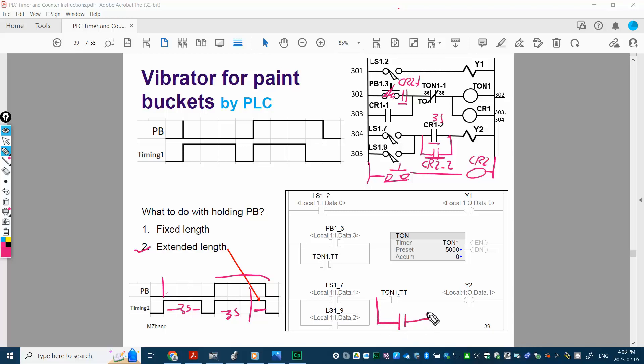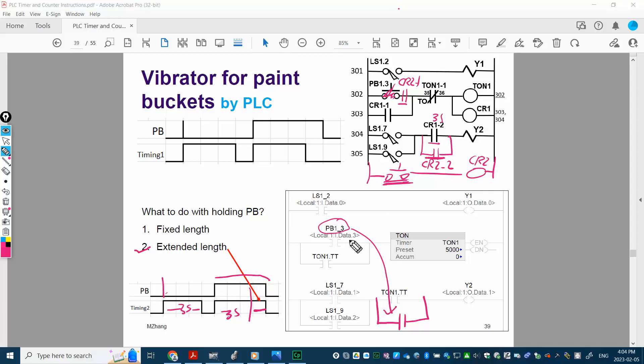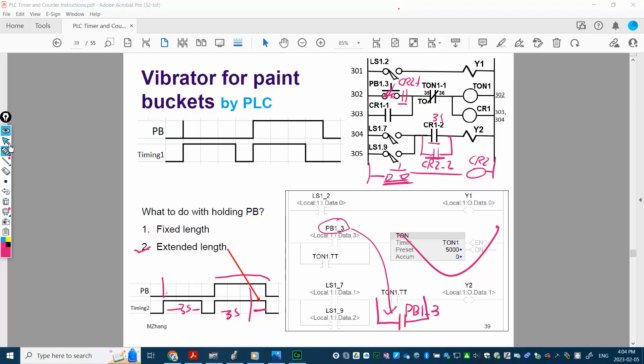In PLC, the solution becomes much cleaner. We don't need all those control relays. We just create another parallel branch. Because once the push button is connected to PLC, it becomes a tag — a memory bit — not a physical contact limited to one set. In the relay design, there's only one set of contacts from the button. But in PLC, a memory bit has unlimited use. So you can use PB1 again in the parallel branch. The PLC solution is even better — very easy to improve and change compared with the electrical solution.